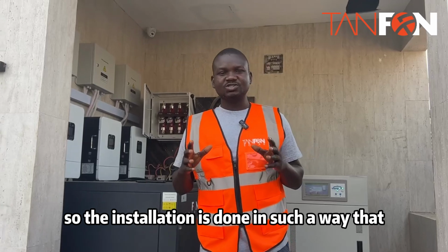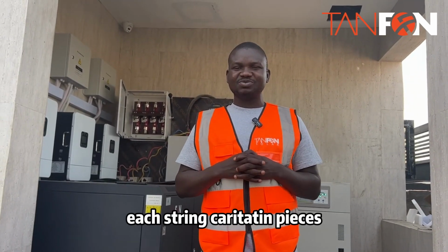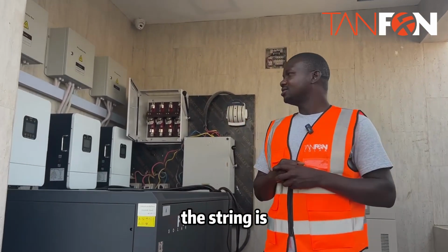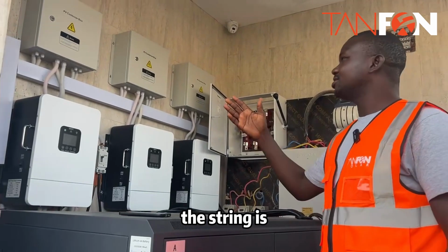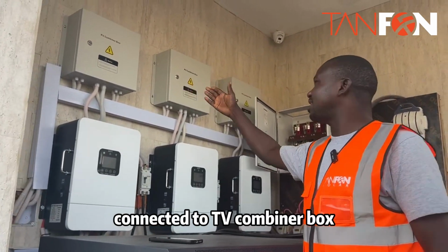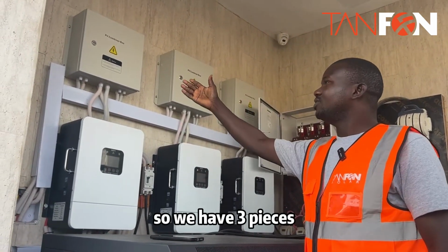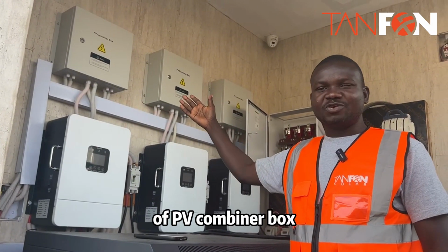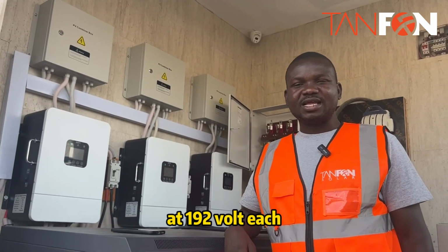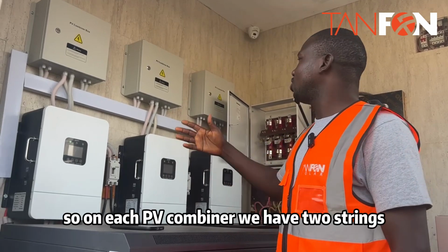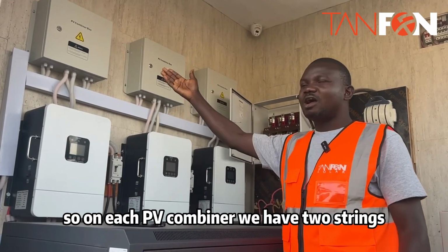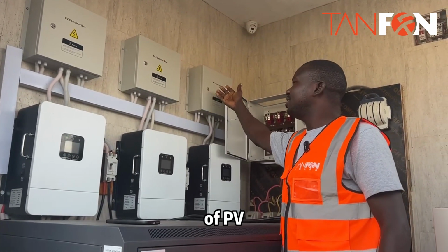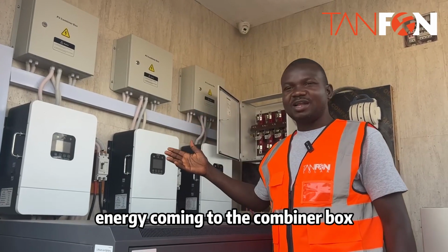We have 78 pieces of 600 watt panels, giving us 46.8 kilowatts of solar energy. The installation is done such that each string carries 13 pieces of PV, and the string is connected to a PV combiner box. We have 3 PV combiner boxes at 192 volts each, with 2 strings of PV energy coming to each combiner box.